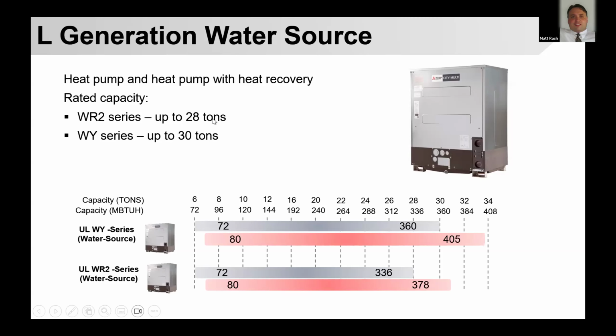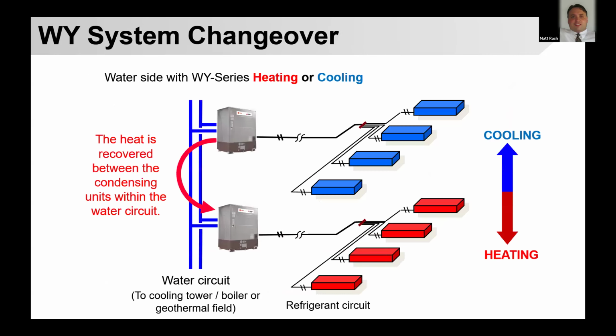We have two variations available. This is fairly common among different manufacturers, but we offer a heat pump changeover system up to around 30 tons, and a heat recovery system up to around 28 tons — a much larger module size than conventional water source heat pump layouts. Again, you have a water side heat sink, which for geothermal would be your geothermal well field, typically exchanging or rejecting heat to that.